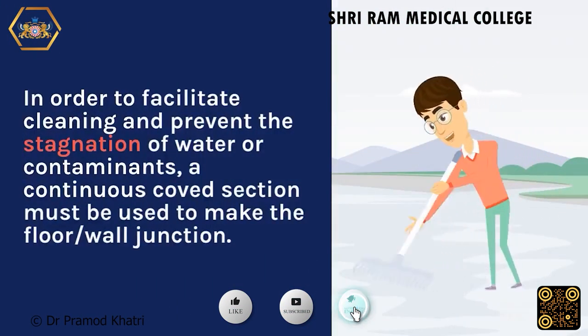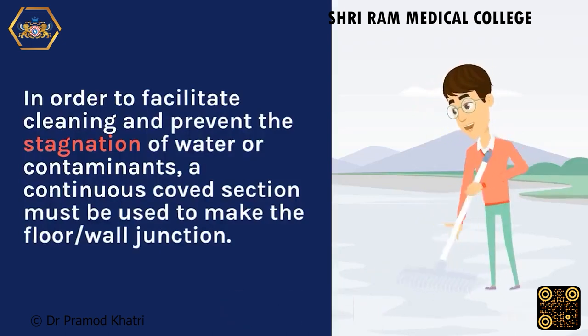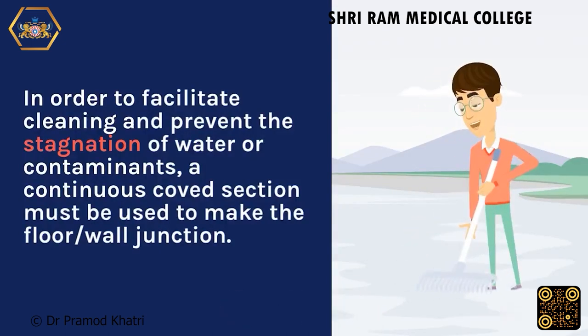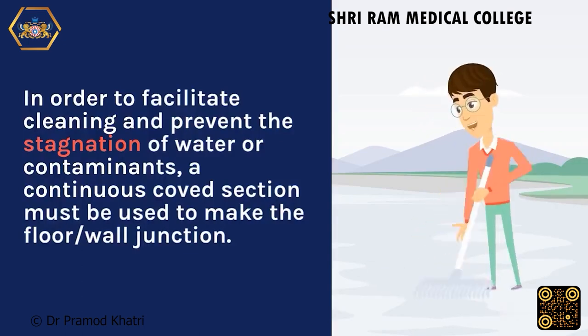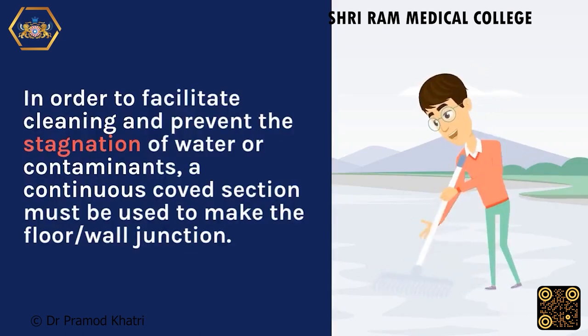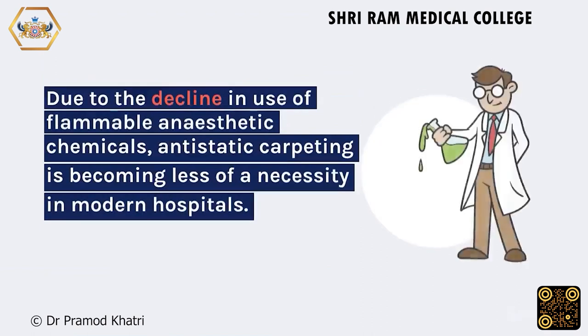In order to facilitate cleaning and prevent the stagnation of water or contaminants, a continuous coved section must be used to make the floor/wall junction. Due to the decline in use of flammable anesthetic chemicals, anti-static carpeting is becoming less of a necessity in modern hospitals.